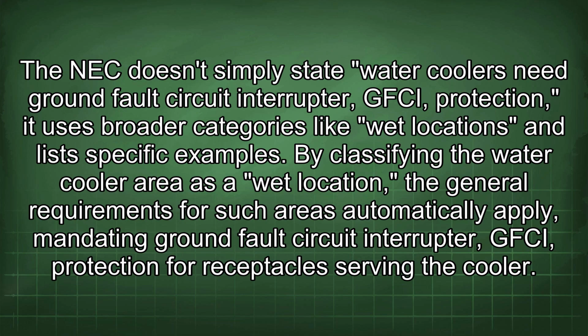It uses broader categories like wet locations and lists specific examples. By classifying the water cooler area as a wet location, the general requirements for such areas automatically apply, mandating GFCI protection for receptacles serving the cooler.